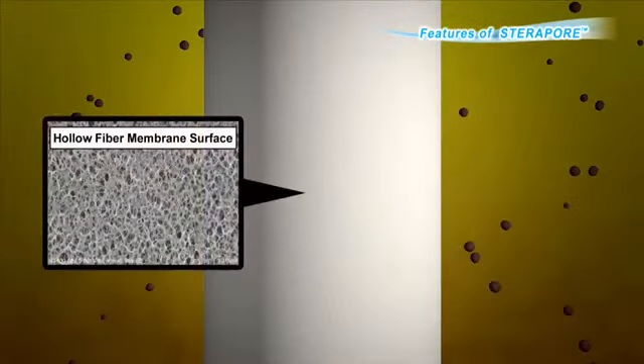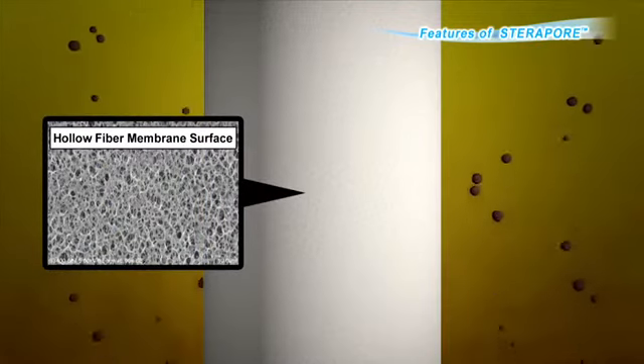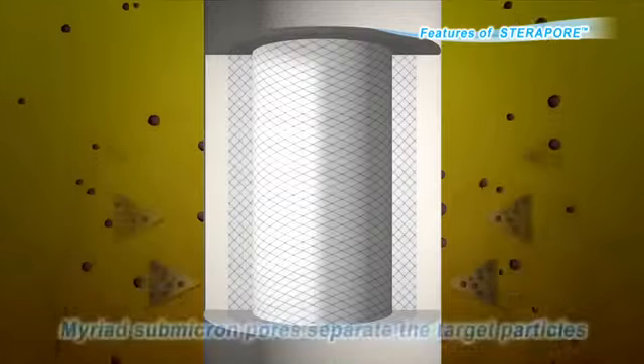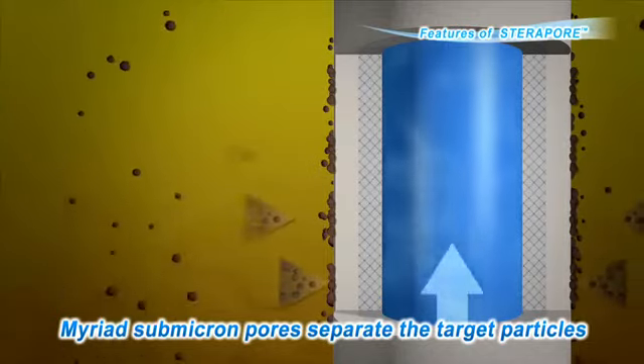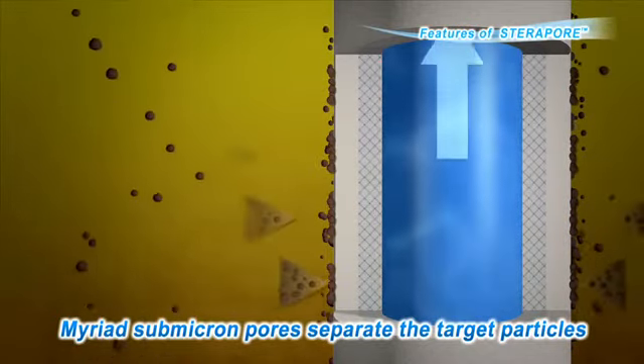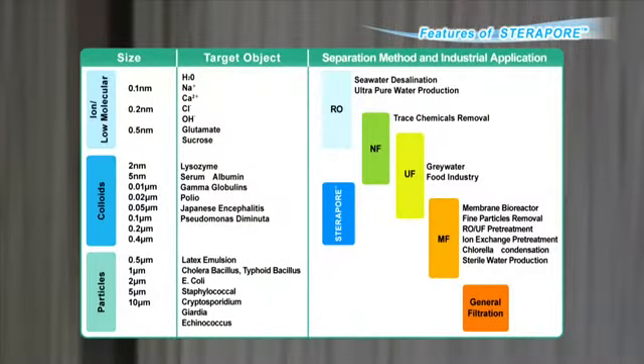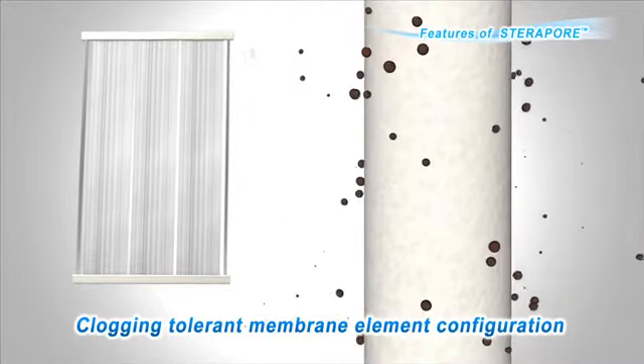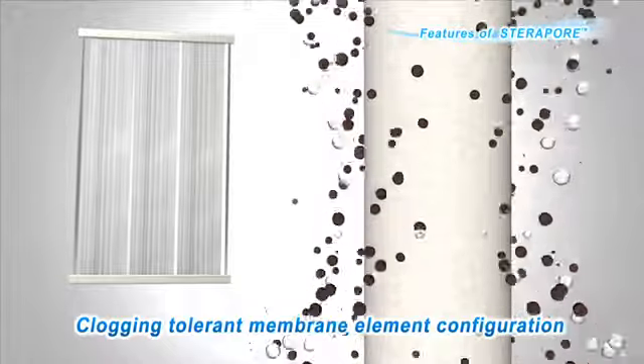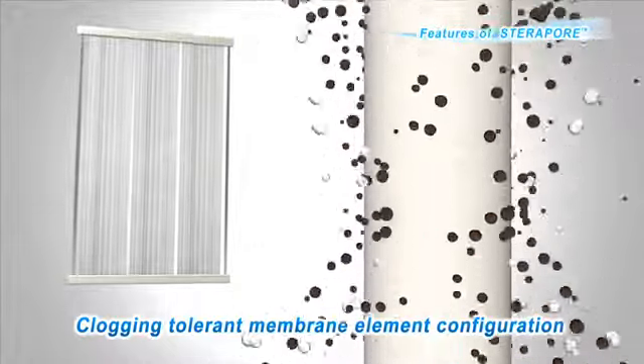On the PVDF layers of the hollow fiber membrane surface, there are countless small pores which separate the target particles. There are two types of hollow fiber membranes — called the UF and MF membranes — which can be selected to match the target material to be removed. By collecting and processing hollow fiber membranes into a flat bundle, a membrane element is formed, which has a very good structure for membrane cleaning by aeration, ideal for high turbidity operations at MBR plants.